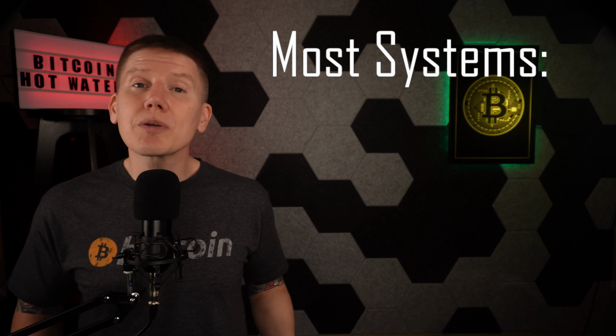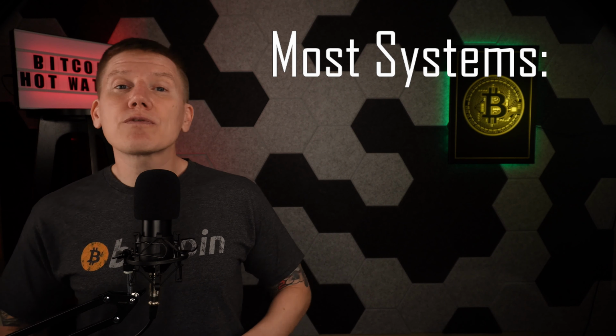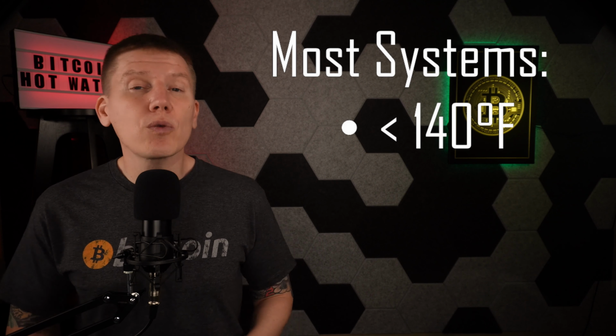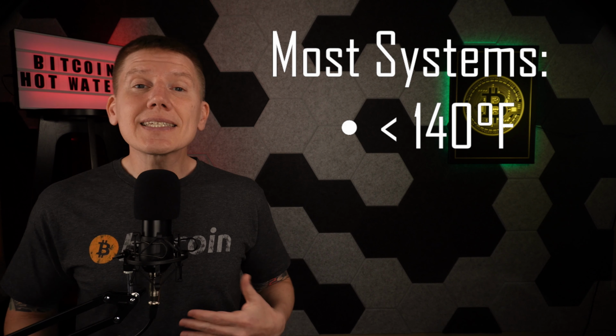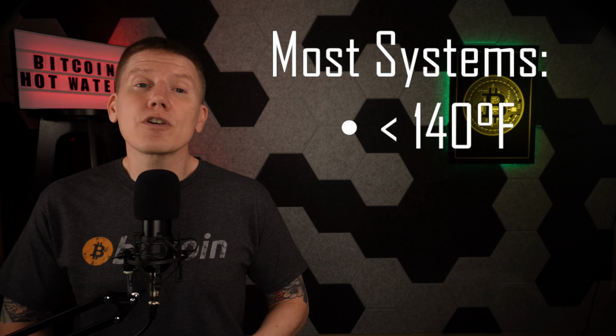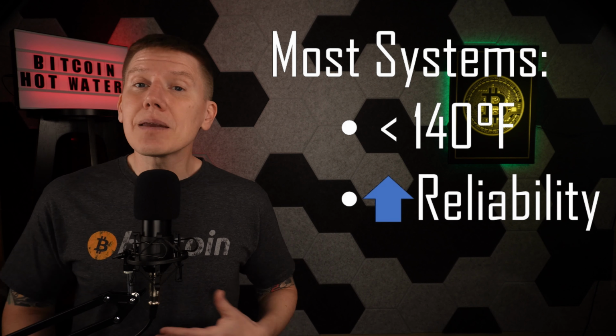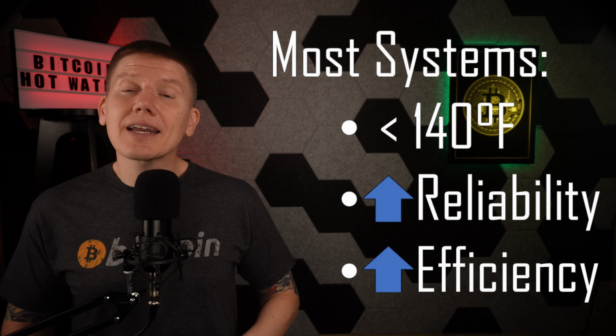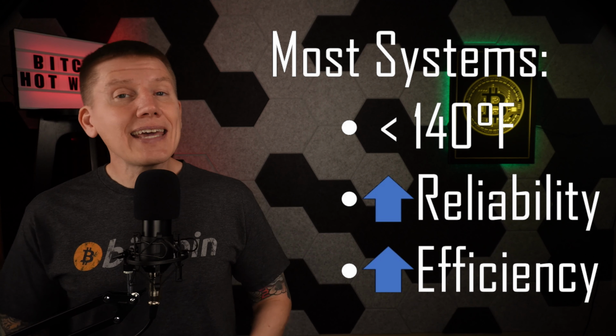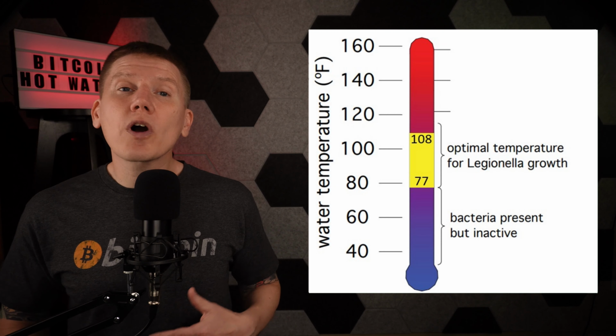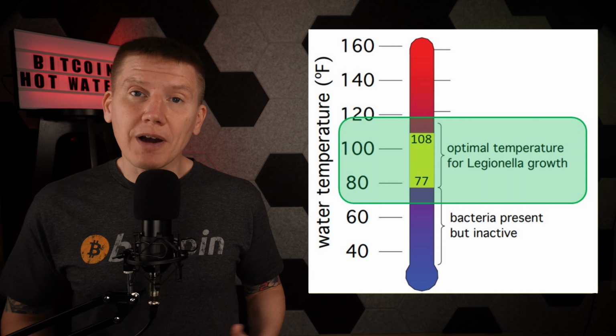However, most immersion mining systems are going to generate fluid temperatures much lower than 140 degrees since keeping miners cool increases their long-term reliability and mining efficiency. Depending on how the system is designed and how it is operated, this can put water temperatures right in the sweet spot for bacteria growth. And so Bitcoin water heating systems must be designed with this risk in mind.